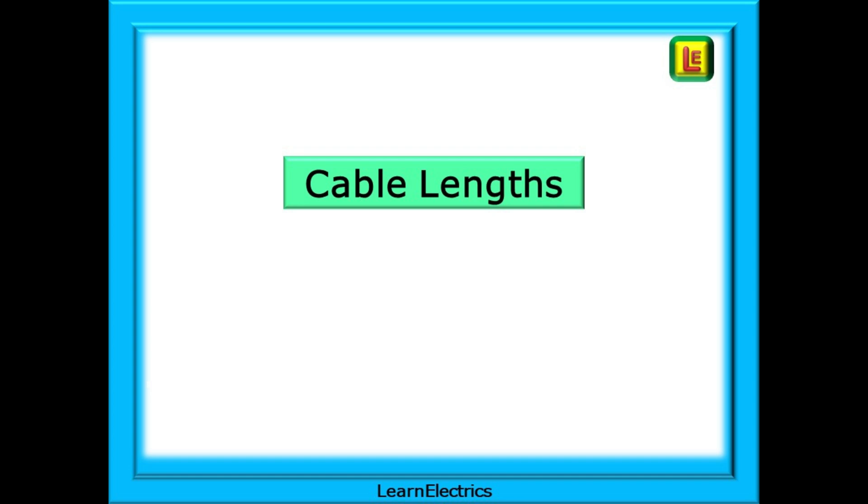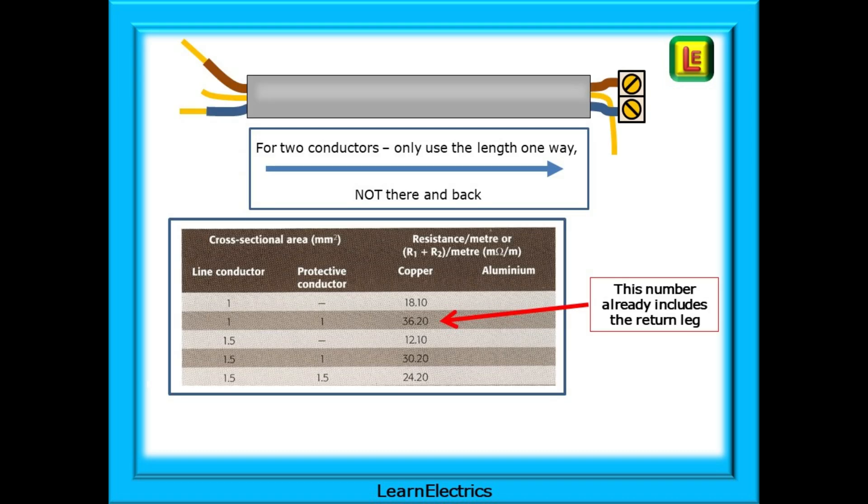A little more information for you on cable lengths. Lots of questions asked. If I have a 10 meter length of twin and earth and want to calculate the R1 plus R2, do I use 20 meters as the length, 10 meters for the line and 10 meters for the earth? The answer is no. For two conductors, we only use the length one way, not there and back. The milliohms values shown in the table takes into account the length of each conductor.